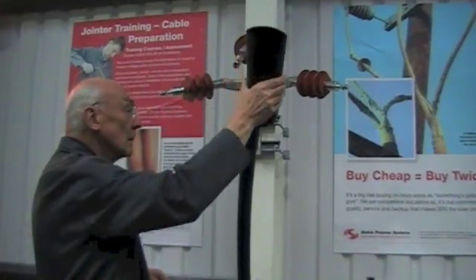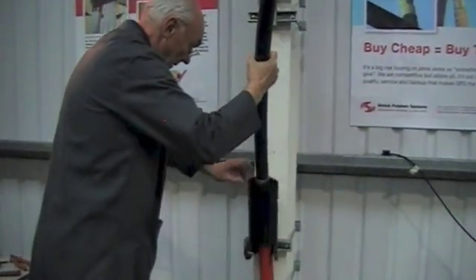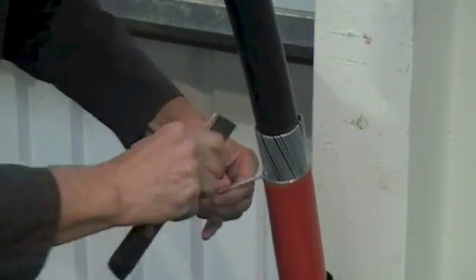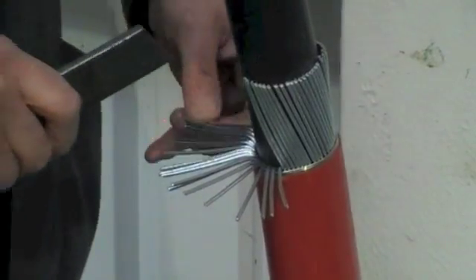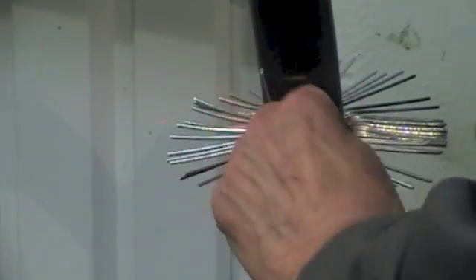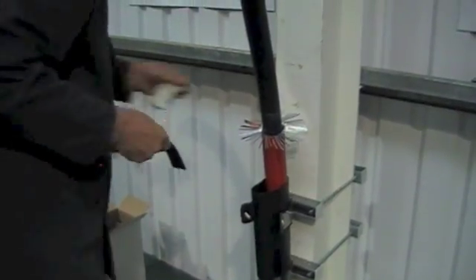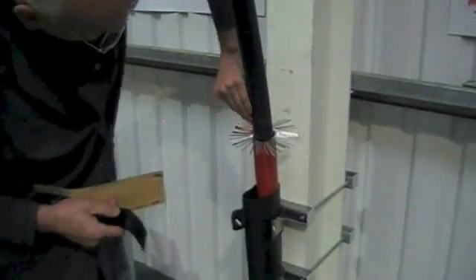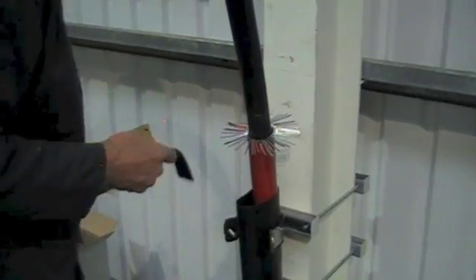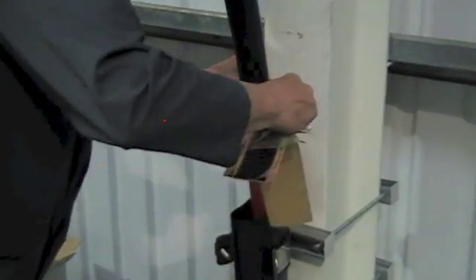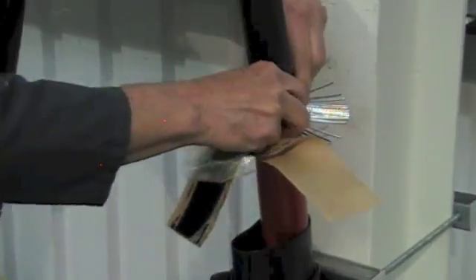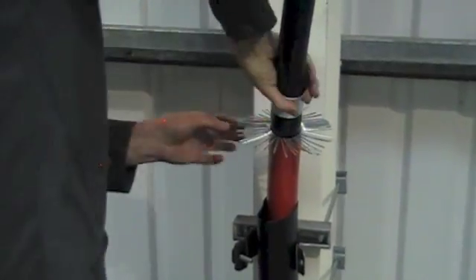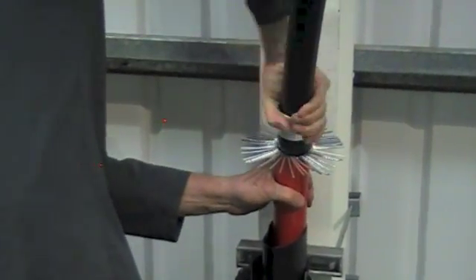Our binder may assist in splaying the armor wires that we'll be showing soon. Position the armor earth heat shrink cover sleeve before bending back the armor wires. Remove the backing tape from the black mastic tape, apply around the inner bedding, and fit the armor support ring as shown.